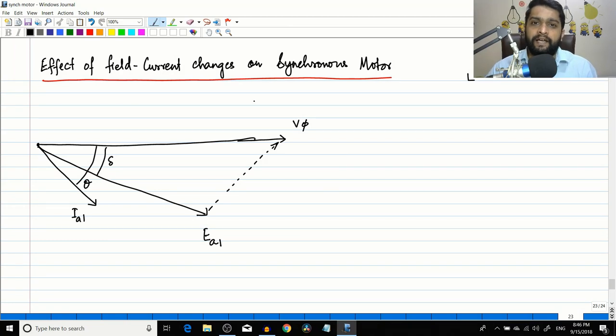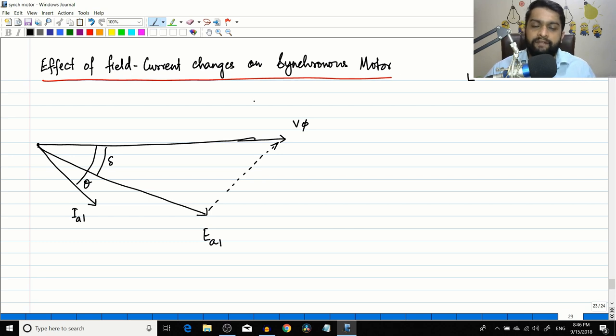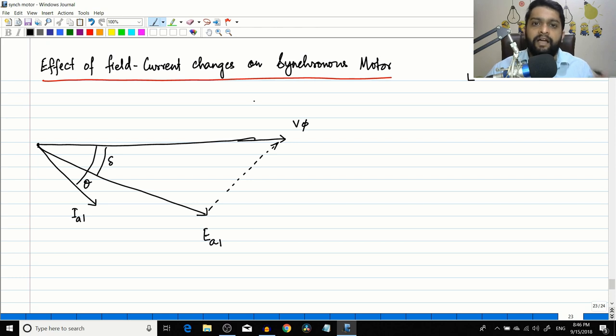In the previous sessions we have seen the effect of changes of load on the synchronous motor - the lead section and lag section were considered separately. In the lead section, as you increase the load, delta increases, Ia increases, and cos theta actually improves. As you continue increasing load into the lagging side, Ia and delta increase but power factor becomes more and more poor as theta increases.